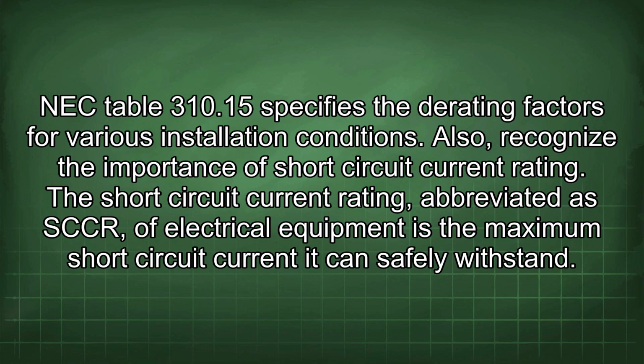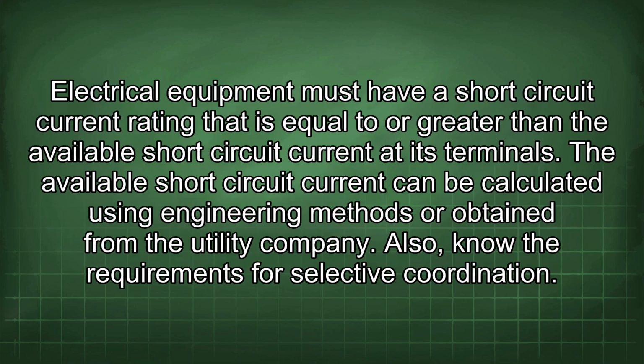Also, recognize the importance of short-circuit current rating. The short-circuit current rating, abbreviated as SCCR, of electrical equipment is the maximum short-circuit current it can safely withstand. Electrical equipment must have a short-circuit current rating that is equal to or greater than the available short-circuit current at its terminals. The available short-circuit current can be calculated using engineering methods or obtained from the utility company.